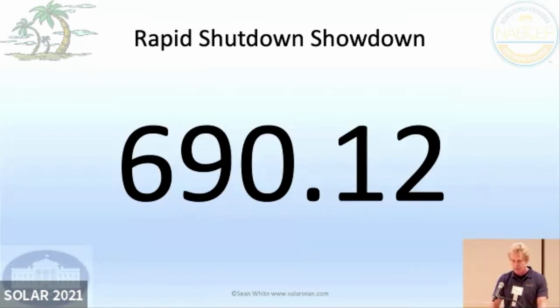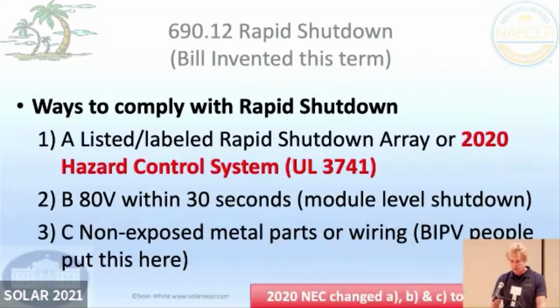So rapid shutdown, 690.12, it's always something to talk about that people like to get excited about too. And there's 3 ways to comply with rapid shutdown. Traditionally, most everybody does number 2, module level rapid shutdown. 2 modules in series is over 80 volts and 1 module is over 40 volts almost all the time. Rapid shutdown has to do module level, 80 volts in 30 seconds within the array.